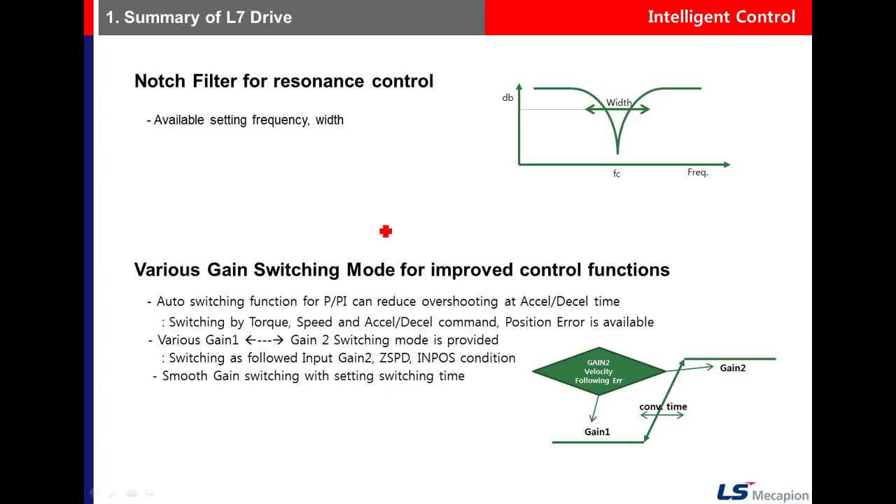There are gain switching modes. First is P/PI switching, which converts to P control to reduce overshoot at acceleration time — P uses proportional gain only, while PI uses proportional and integral gain. Second is gain 1 and gain 2 switching, where you have two sets of gain parameters and can switch between them according to the situation.